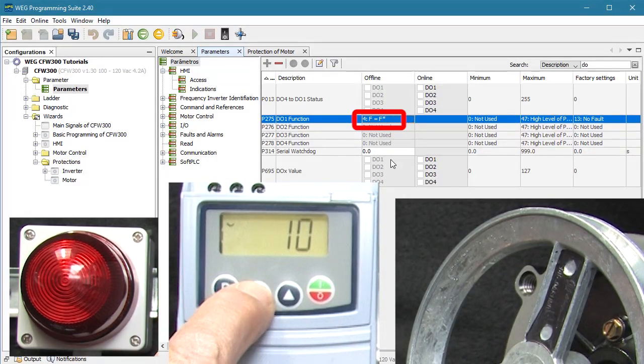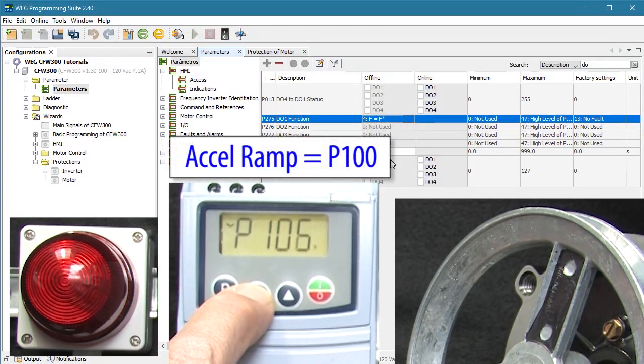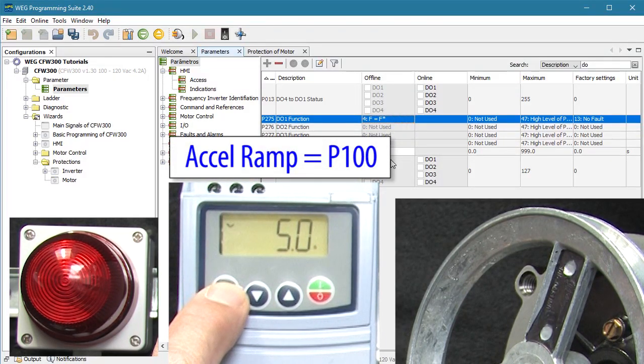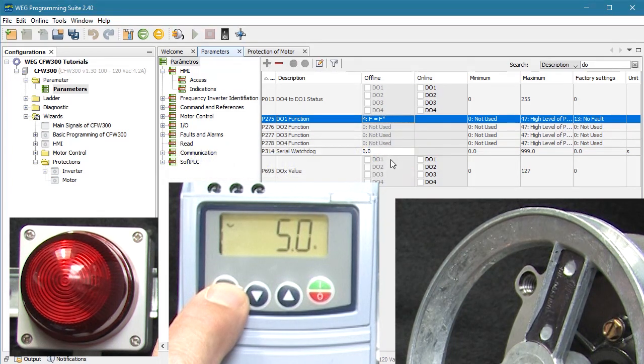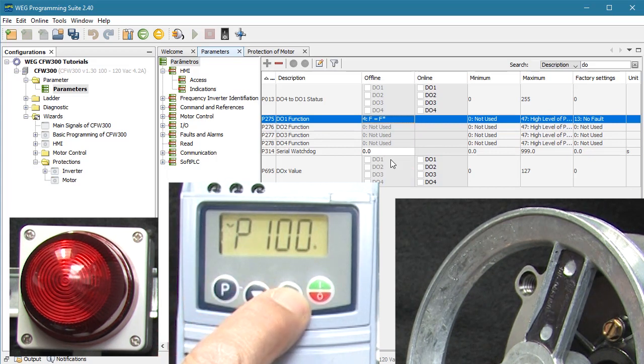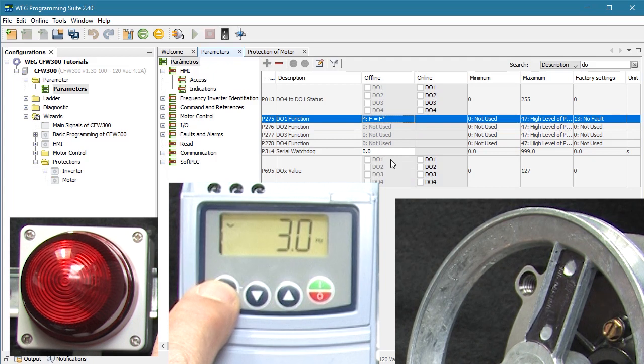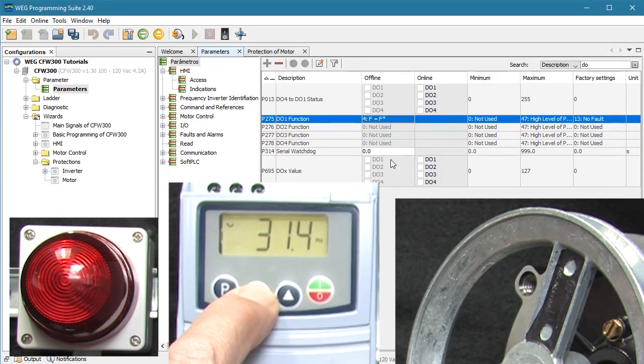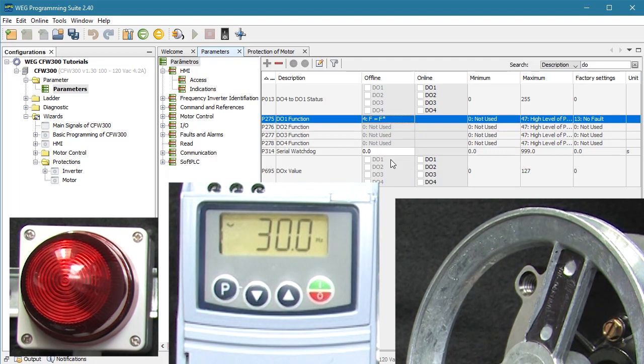So I'll go back to parameter 275 and change it to a 4. The acceleration ramp defaults to 5 seconds — that's 5 seconds to get to 60 Hz, which is a good number for this demo. Let's set the frequency we want to ramp to at 30 Hz. That's parameter 121 because we are using the keypad for frequency reference entry. So we expect the drive to ramp up to 30 Hz over 2.5 seconds and when it gets to 30 Hz, the indicator should turn on. Let's try it.